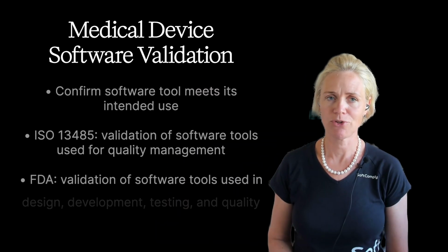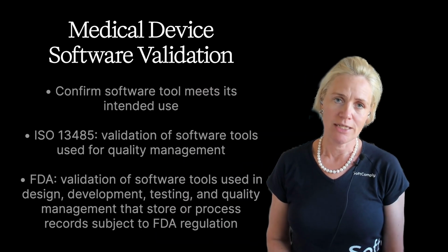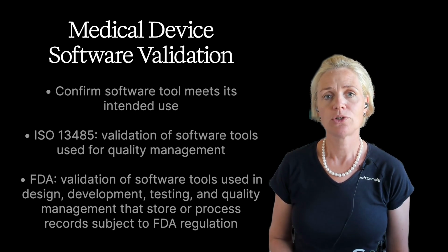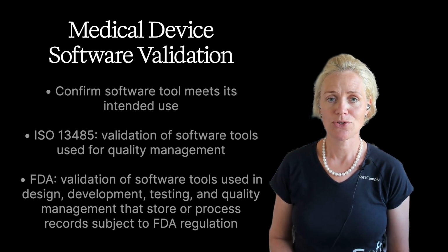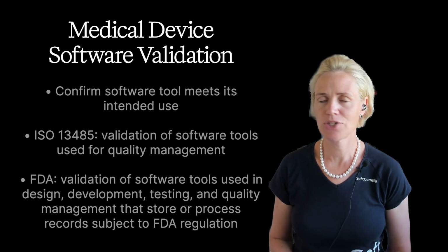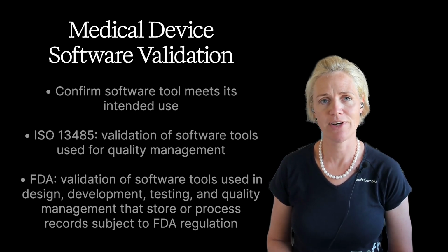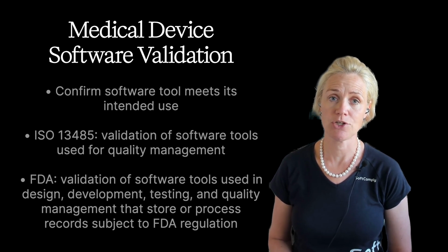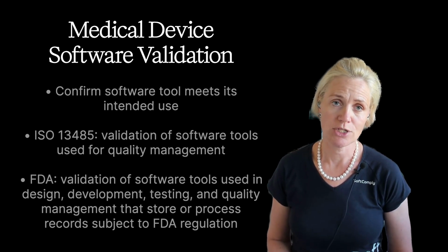But let's start with some context. In the medical device regulations, validation means confirming through objective evidence that a software tool consistently meets its intended use, essentially verifying that it does what it is supposed to do. International standards like ISO 13485 mandate validation of software used for quality management, including initial validation as well as revalidation after changes, proportionate to the risk.